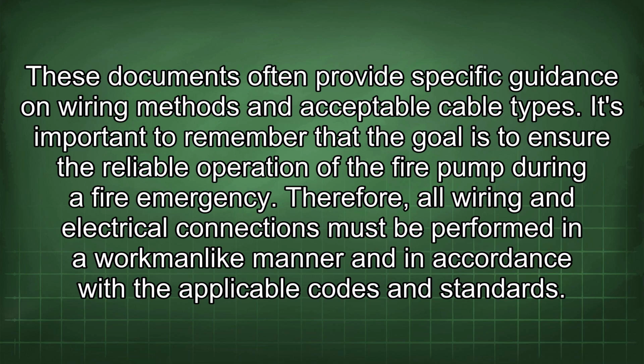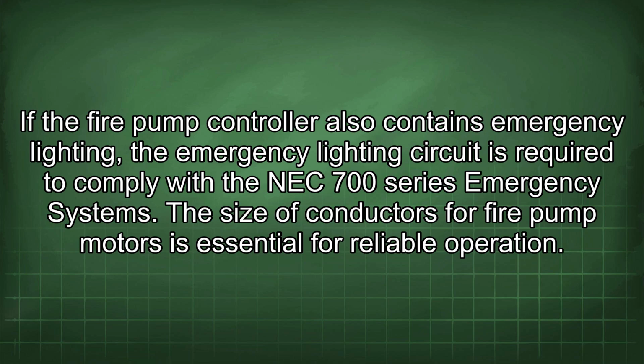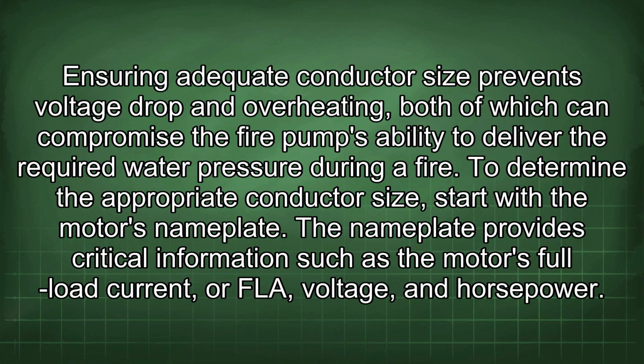It's important to remember that the goal is to ensure the reliable operation of the fire pump during a fire emergency. Therefore, all wiring and electrical connections must be performed in a workmanlike manner and in accordance with the applicable codes and standards. If the fire pump controller also contains emergency lighting, the emergency lighting circuit is required to comply with the NEC 700 series emergency systems. The size of conductors for fire pump motors is essential for reliable operation. Ensuring adequate conductor size prevents voltage drop and overheating, both of which can compromise the fire pump's ability to deliver the required water pressure during a fire.